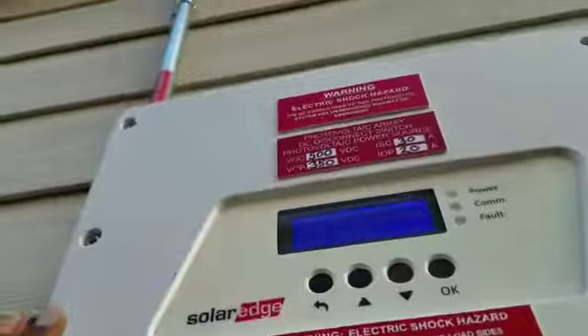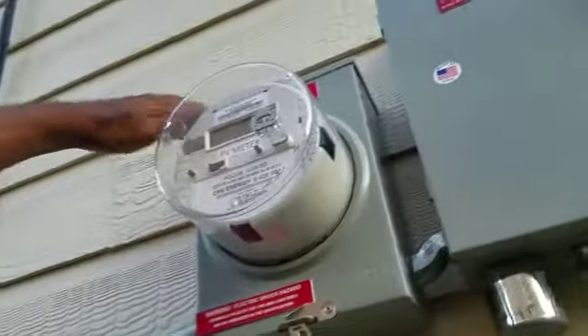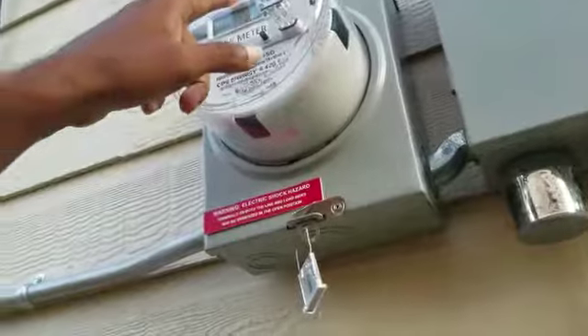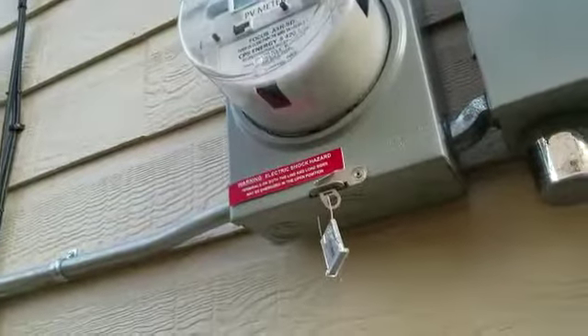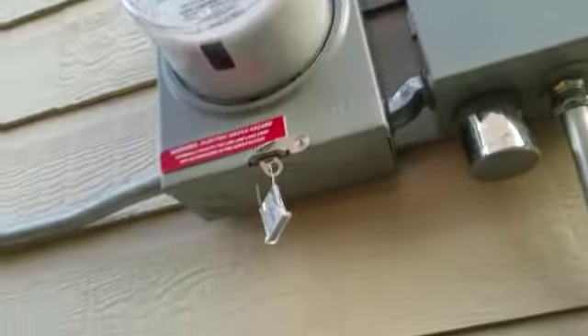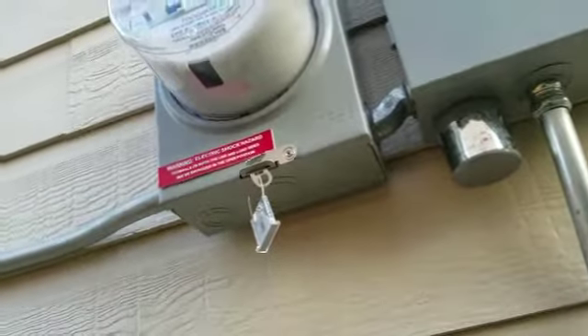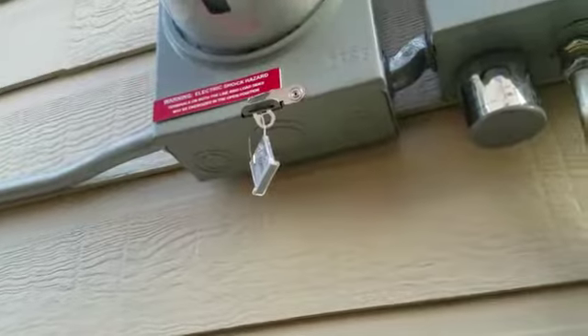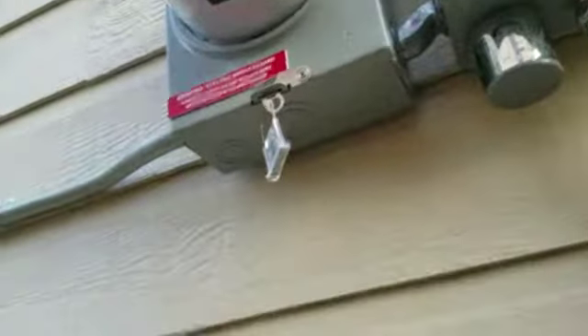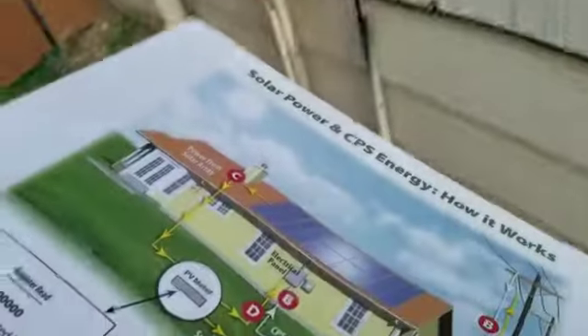Now this is the inverter, and then we have the same consolidated information here in the photovoltaic meter. There we can see the breakdown. And here we can see its total, it had generated 184 kilowatts. Yesterday morning, how much was it? 143? Yeah. So 143 minus 184, it's around 42 kilowatt hours. This energy is enough to power at least 10 homes in India.